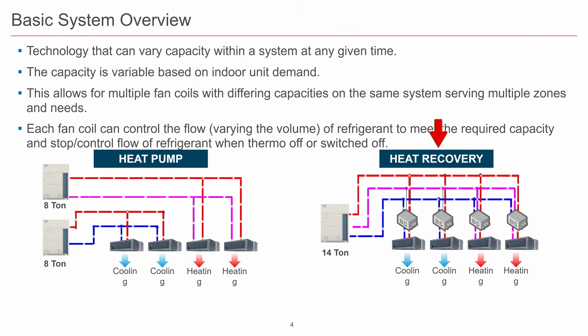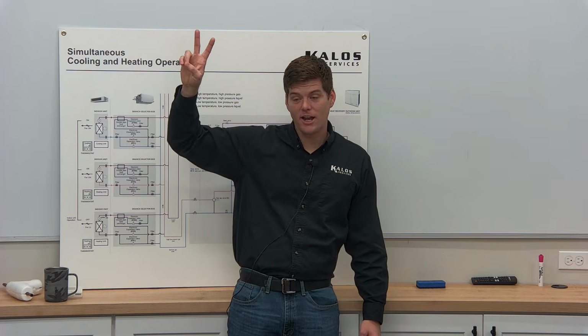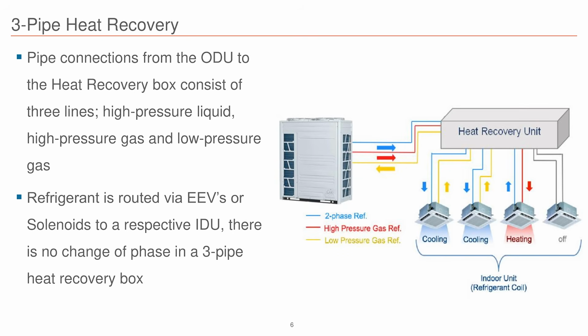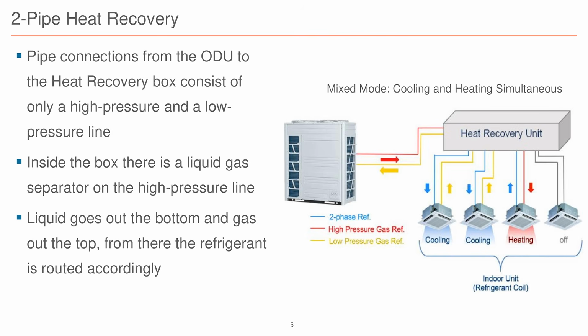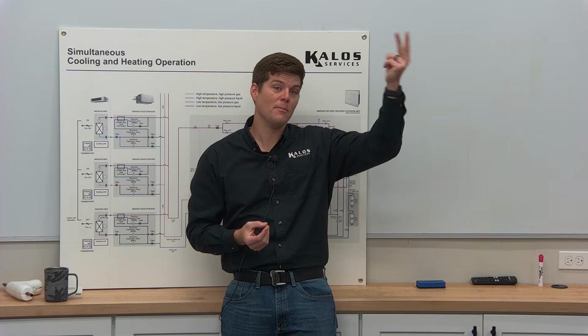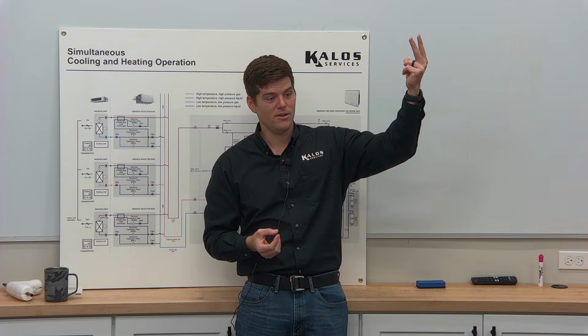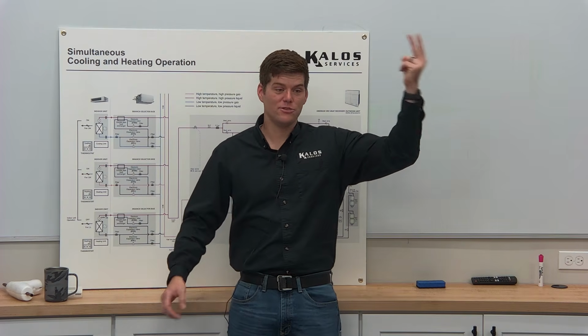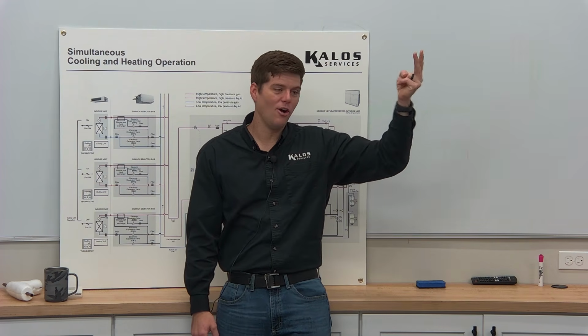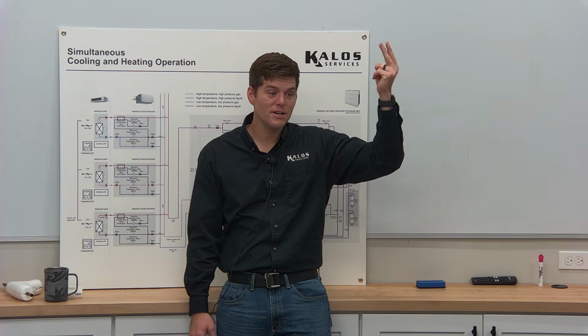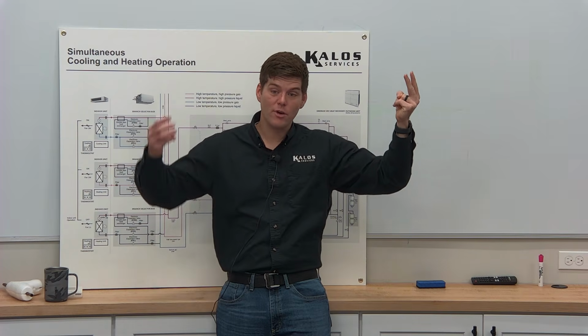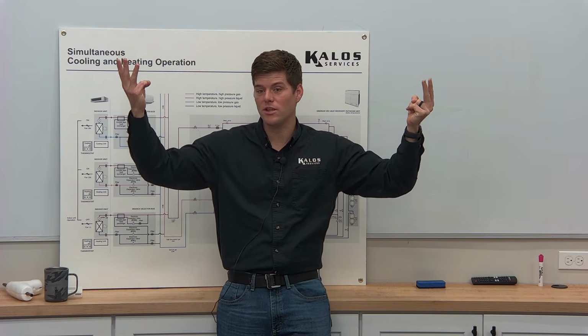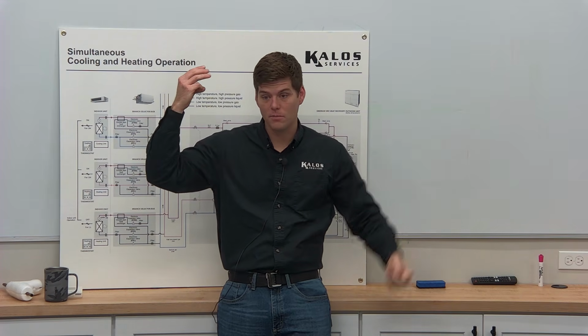You'll notice that we've added another refrigerant line. In the VRF world, this is Daikin. There are two different kinds of VRF heat recovery systems. There is a 3-pipe and there is a 2-pipe. Mitsubishi fits into the 2-pipe. They've owned and dominate that market with the 2-pipe heat recovery, with the claims of less copper piping on installation, all these other benefits and features that come with a 2-pipe system. But it is limited, unfortunately. Everyone else uses 3-pipe.